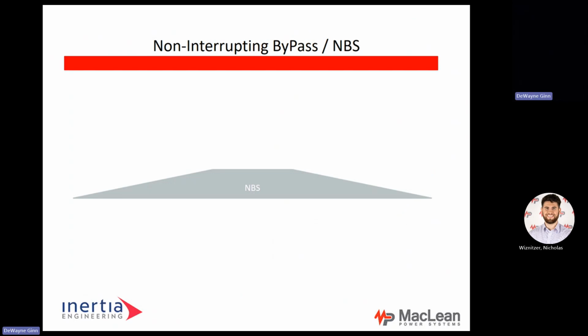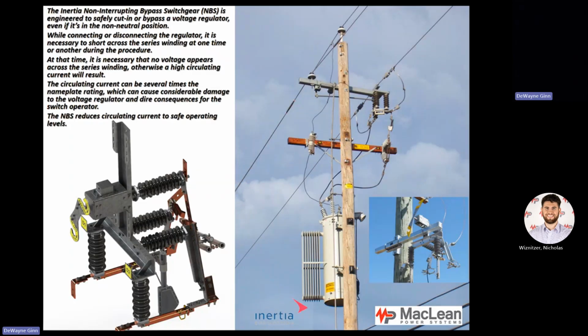MPS, non-interrupting bypass switches. This is the one for voltage regulators. A voltage regulator on that pole is a very dangerous piece of equipment. What a voltage regulator does is, if there's a dip in the power, it starts ratcheting up to try to get more energy through the line. If there's too much energy in the line, it ratchets down to try to eliminate that energy in the line. There's a neutral position in it.